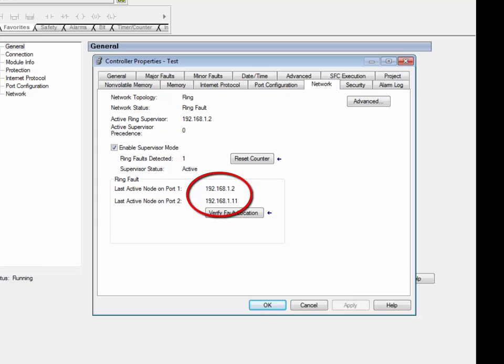In this example, the ring break is between nodes 192.168.1.2 and 192.168.1.11. Maintenance personnel can go and investigate the cable between these two nodes on the Ethernet IP network.